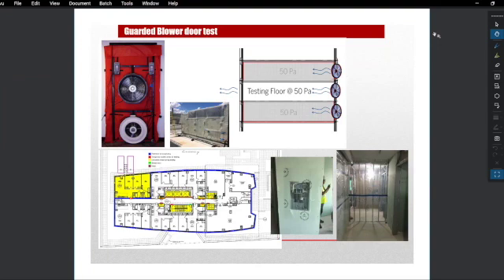Obviously there are ways around it. It takes time and effort to seal the panels, seal the hoist run, and make sure trades aren't on the job when this is happening, since it will interfere with work and the schedule. We've attempted this on other projects, with success and without success. Either way, the guarded blower door test is just a way of trying to see if you're going to hit the final blower door number, and there's no guarantee you'll actually pass the final test just because a guarded blower door test went well, because you could have fake results from sealing that isn't applicable to the permanent condition.